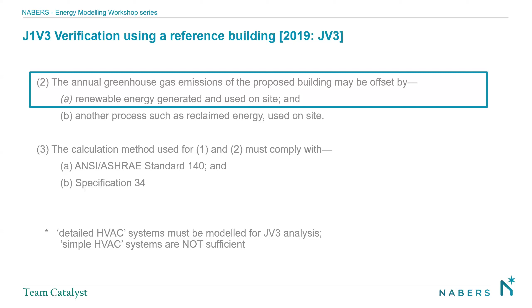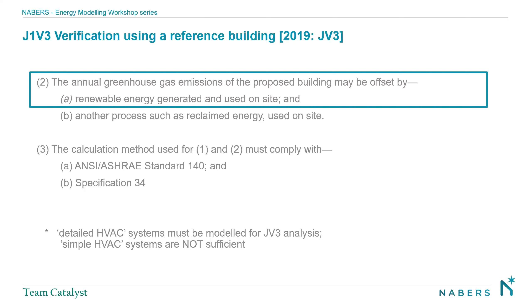By this time you would have recognized that even for JV3, you have to model a fairly detailed air conditioning system. You can't do a theoretical, simple HVAC system—that's not allowed. That's typically because when you are testing thermal comfort, real systems take a little while to get up to speed, and in the first couple of hours, if your system is not well controlled, you may lose thermal conditions. There are some fairly clear definitions in the code as to when you are testing for thermal comfort, but I won't go into that right now.